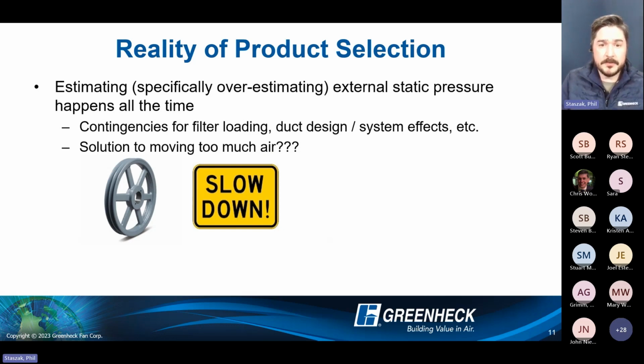Now, the downfall to anything on a forward curve fan, which is still going to be in your 25,000 CFM and higher airflow ranges, is anything that's above 10 horsepower, you're now in fixed pulley arrangement. So there's no more drive adjustability on the motor side to be able to slow a fan down by turning a pulley in or out a 1/2 a turn at a time. They're fixed pulleys. So if you're in that overload state, first off, you're throwing a dart at the system to just try and calculate what sheaves need to be changed out if you don't have a VFD. And then you're trying to balance the system down from there.